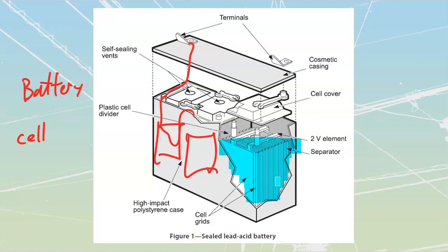Distillation is just heating stuff up till we evaporate it. We leave all the contaminants behind. Do not ever use tap water because you don't know what the mineral content is. Some places, take a look at Greendale out in Chilliwack, that water is like rust red. You stick that inside there, you've got iron chunks inside there, and that battery is going to be shorted out internally and it's going to blow up. You have to use distilled water with that acid that you will have inside of there.